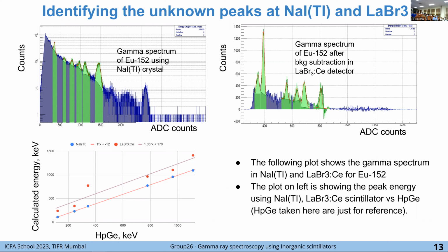And in the right picture, you can see the same picture, but with the lanthanum bromide crystal after subtracting the background of the radioactivity. Then we used our calibration line, calculated our energy for each peak, and compared it with the measurement of this peak using another detector. So you can see a good line, and you can see that the behavior of them is similar to each other.